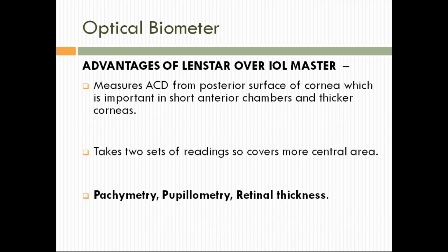So, what are the advantages of LENSTAR over IOL Master? LENSTAR measures the ACD from the posterior surface of the cornea, which is important in shallow chambers and thicker corneas. It takes 2 sets of readings, so it covers more central area. It is also helpful for pachymetry, pupillometry, and retinal thickness measurement.